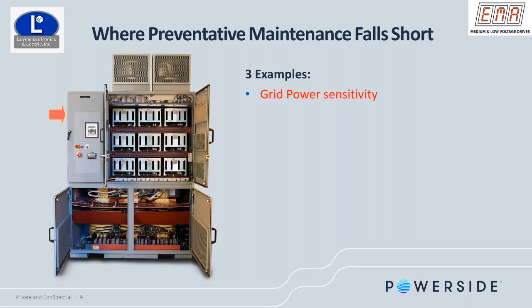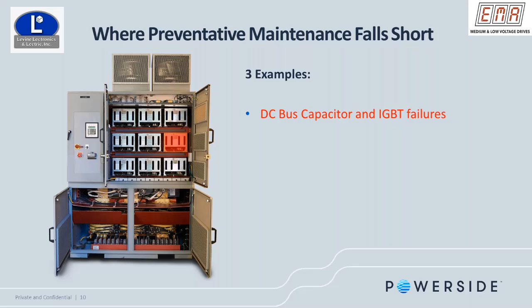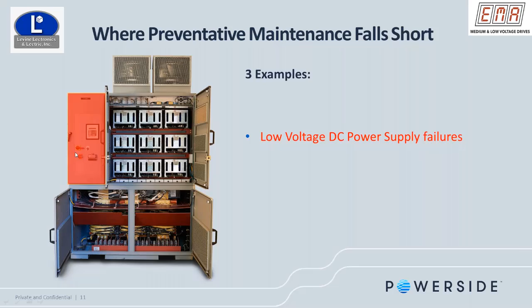On the Siemens medium voltage drives, usually they'll use 9 power cells or 12 power cells, depending on the generation of the drive. This is what we call cascaded brick topology. And this is a whole different webinar if we want to go into details of how that works. And then we have a low voltage DC power supply, which is on the low voltage section of the drive. We have our 24 volts, 15 volts, minus 15 volts, 5 volts power supplies in this compartment of the drive. We also have the environmental sensor that can read temperature, humidity, pressure, and vibration on the transformer section of the drive.